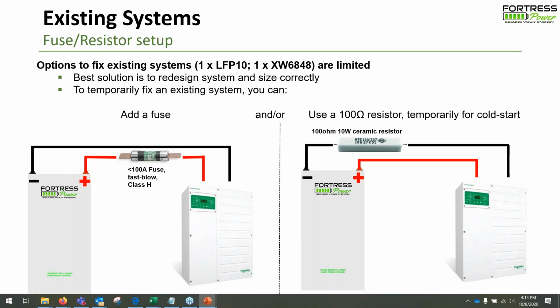To get this pre-charge effect, you can use a 100 ohm resistor temporarily for the cold start. What I mean by temporarily is basically you're going to use alligator clips to connect the negative side of the Fortress to the resistor, and then the resistor to the inverter lead. And this will allow a very low amount of current to start first, maybe 5 amps, probably less than 4 amps. You do this for about a minute, and that will charge the capacitors in the inverter slowly, so that the battery does not get overwhelmed when you try to start the inverter. If this doesn't make sense to anyone, please contact me. I can explain it further. But this is another option. And then you have to be clear that you take off the resistor after you're done. So this is just temporary for starting, right?